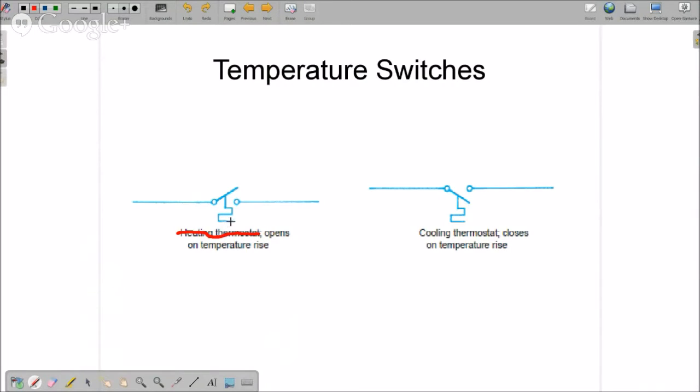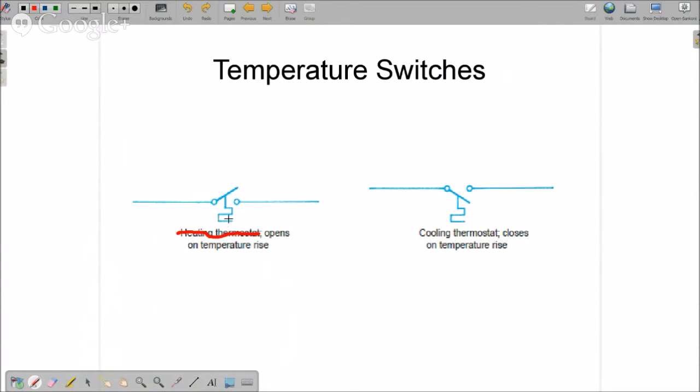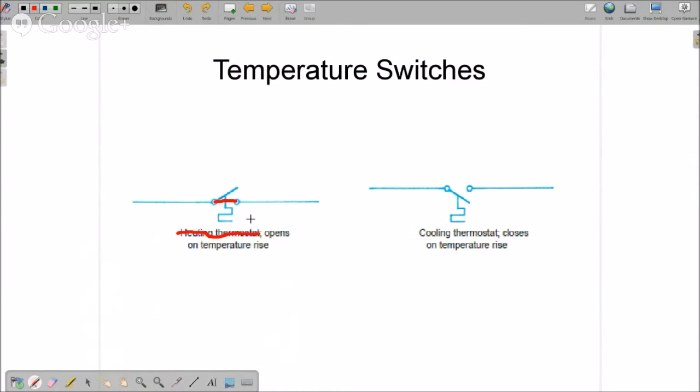This will make more sense in just a little bit. When the temperature increases, it expands this little symbol right here. This is a temperature controlled device when you see that, and it expands and pushes that open. Conversely, if the temperature falls to a certain point, this is going to come back down and close that switch. So this is open on temperature rise. It moves in that direction as the temperature goes up and it closes when the temperature falls.